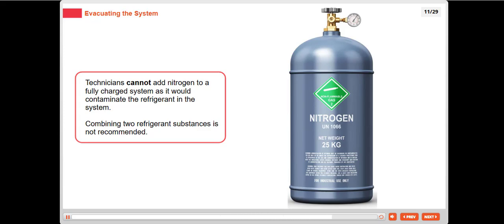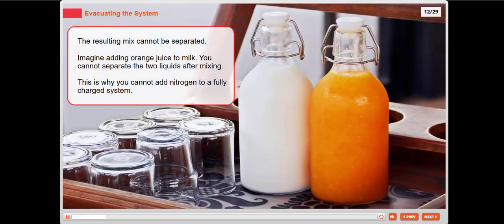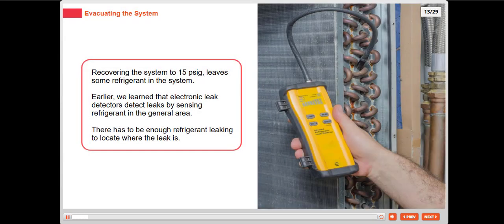The resulting mix cannot be separated. Imagine adding orange juice to milk. You cannot separate the two liquids after mixing. This is why you cannot add nitrogen to a fully charged system. Recovering the system to 15 psig leaves some refrigerant in the system.